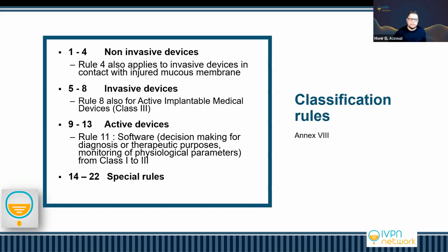There is no discussion. Contraception and prevention of sexually transmissible disease is Rule 15. If it is also a device that is used for disinfecting, cleaning, or rinsing another device, then it's Rule 16. If it's recording X-ray images, then it's Rule 17. If it's used with animal or human tissue, then it's Rule 18. All that is red is a new rule that is coming with EU MDR.